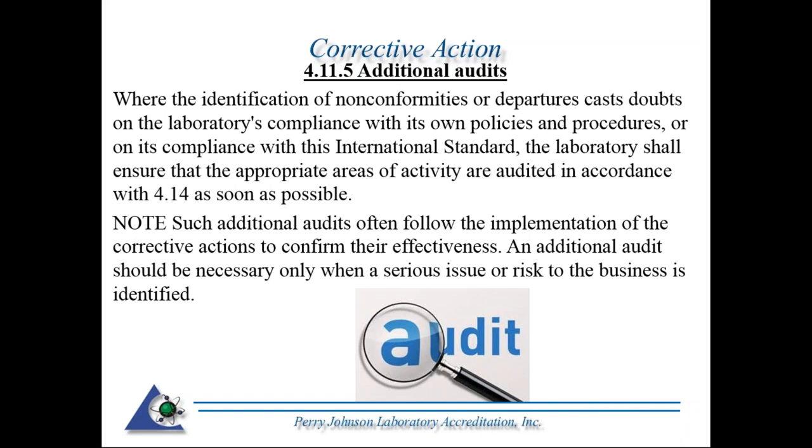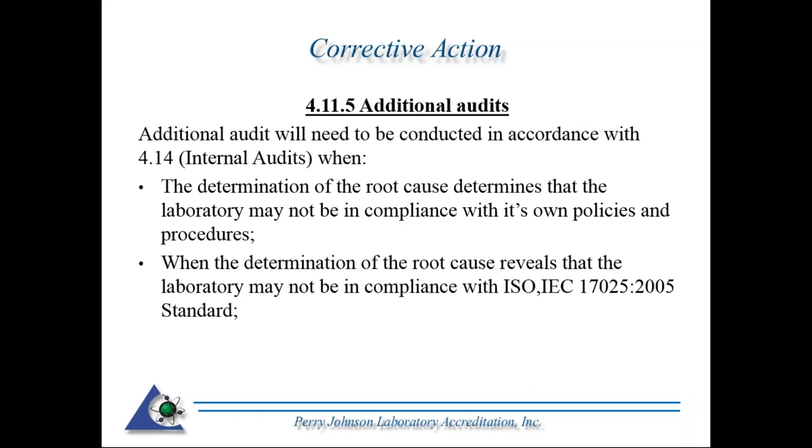Section 4.14, of course, is the section on internal audits. Hence, if the corrective action warrants an additional audit, you would need to revisit section 4.14. Whatever area of the standard the nonconformance or corrective action identified, that section would need to be audited as soon as possible. So what warrants an additional audit? An additional internal audit will need to be conducted in accordance with 4.14 when the determination of the root cause determines that the laboratory may not be in compliance with its own policies and procedures.